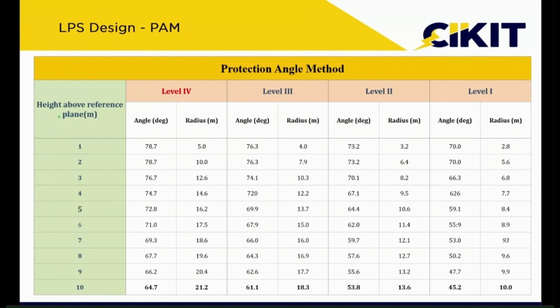This method we have been using for a longer period, and one practical example for this kind of protection angle method is the overhead transmission lines. In the overhead transmission lines, you can observe that there is a ground wire or shield wire at the top of the tower. The purpose of this ground wire or shield wire is to protect the conductor from direct lightning strikes. So that is one example for the protection angle method.